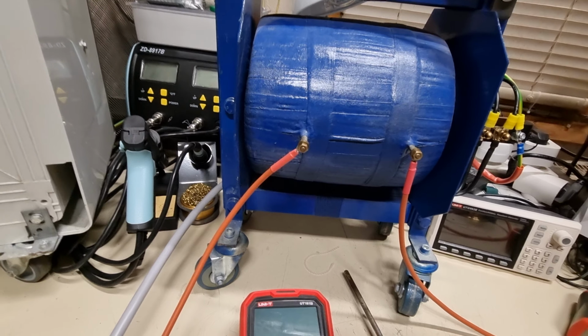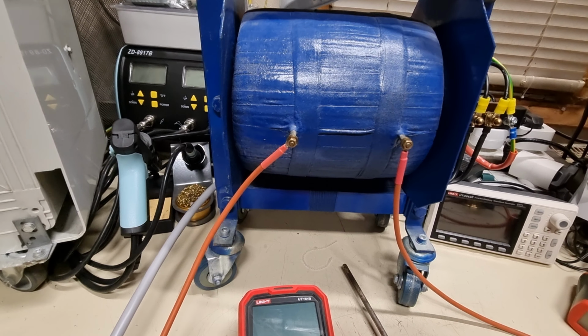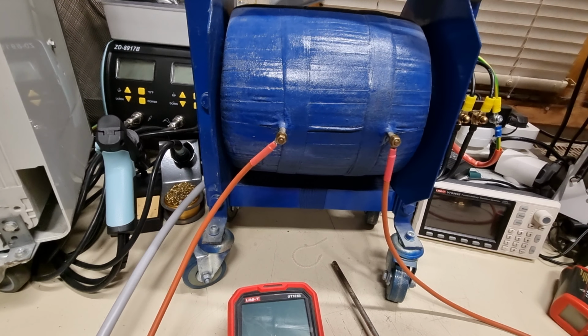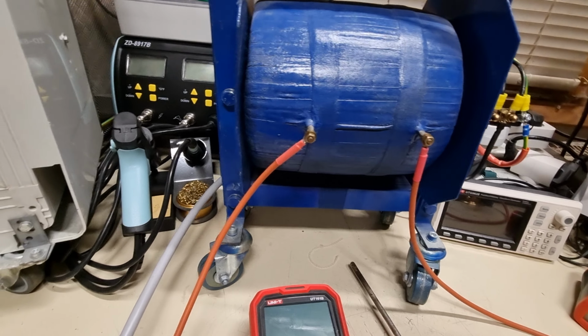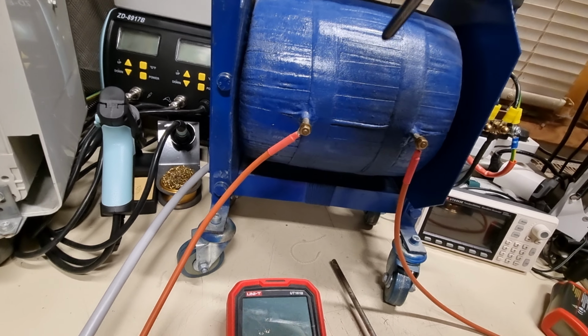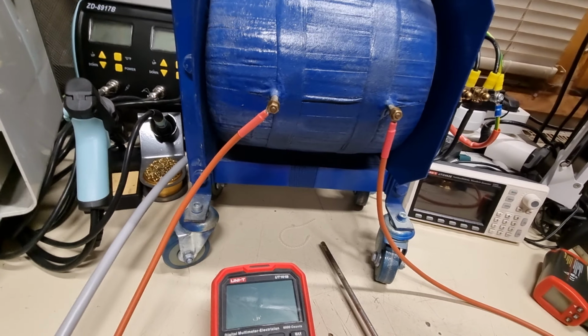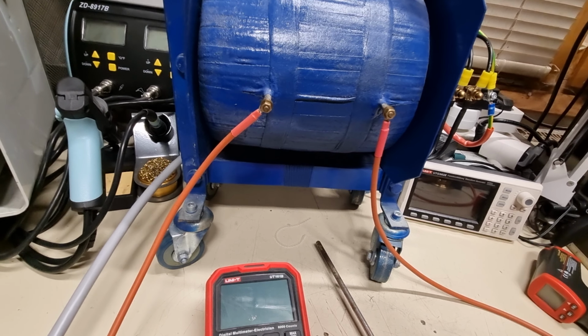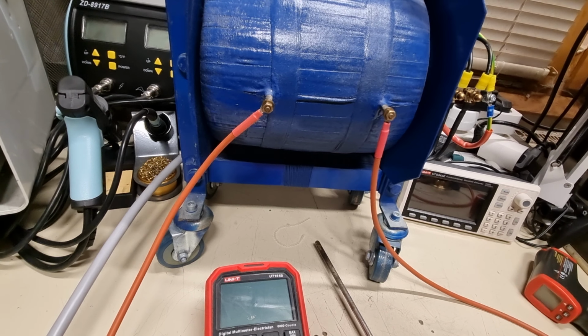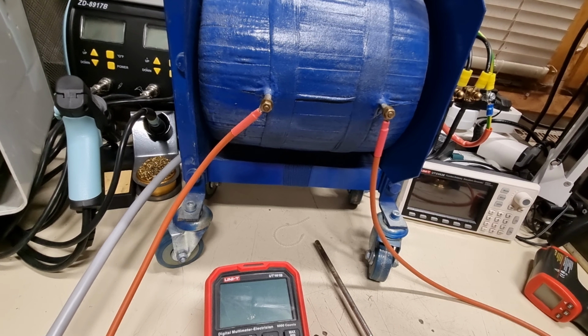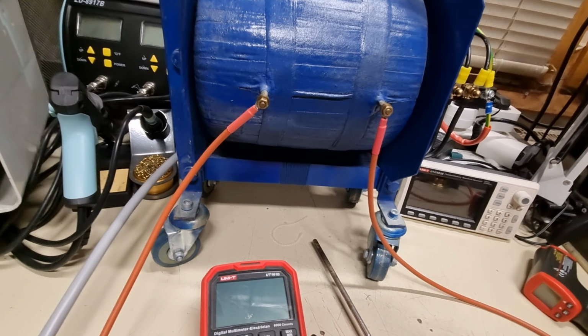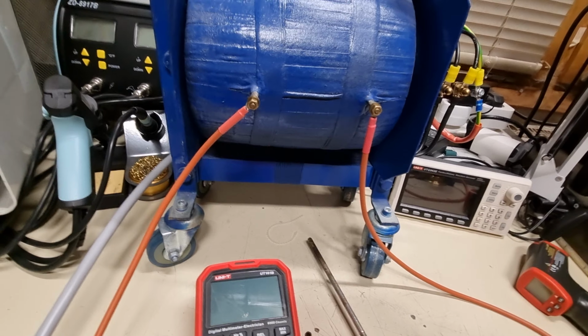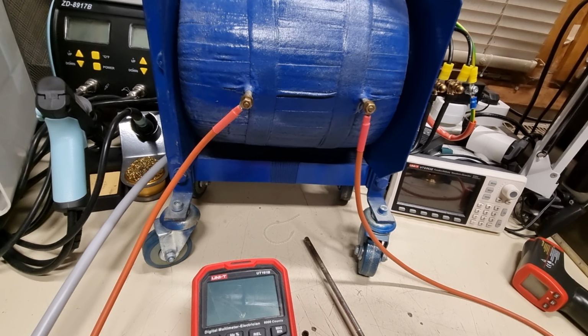For example, we have here a 3.5 kilovolt high voltage transformer. Let's say we are arcing with it and we want to know the temperature inside of the windings. They're epoxied in, so you cannot access them, with fibrous material and resin between the windings and the surface, so you don't know the temperature. There is a way to measure it though, using the resistance of the windings.